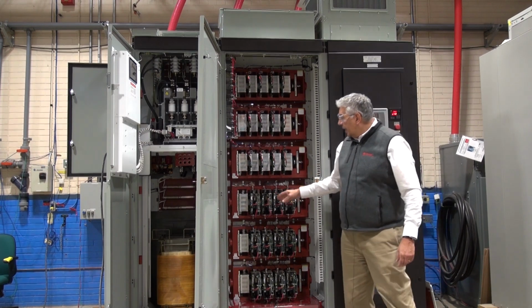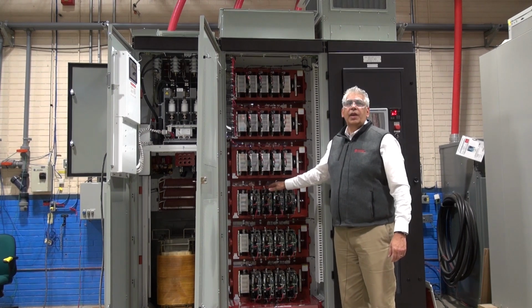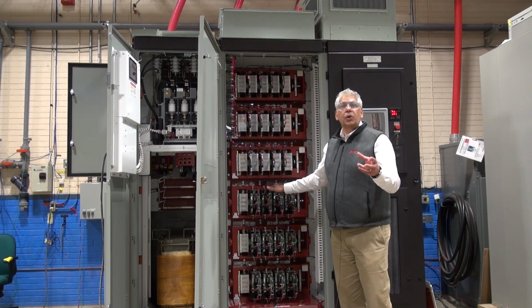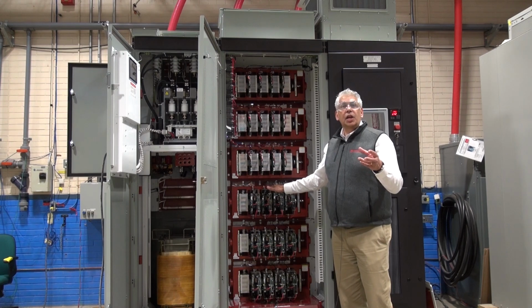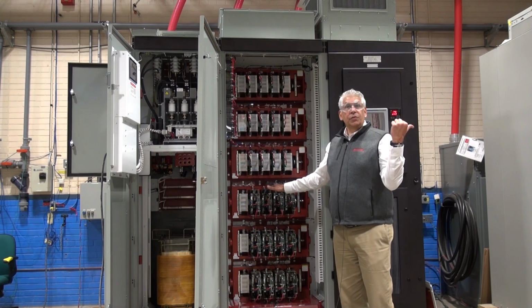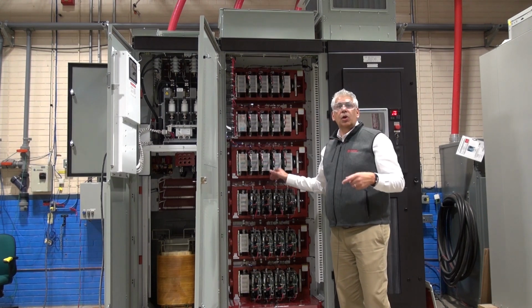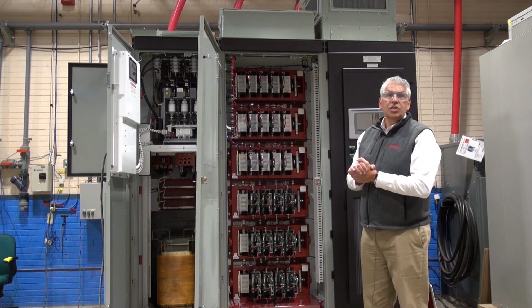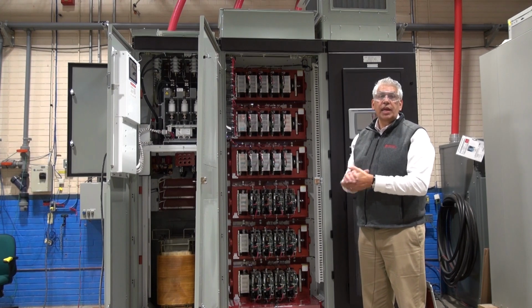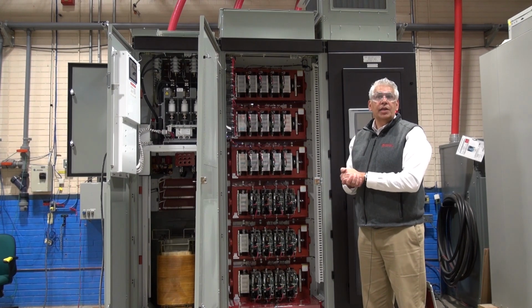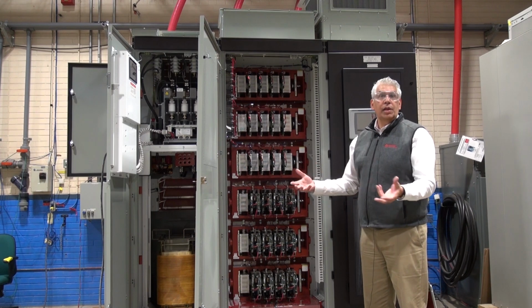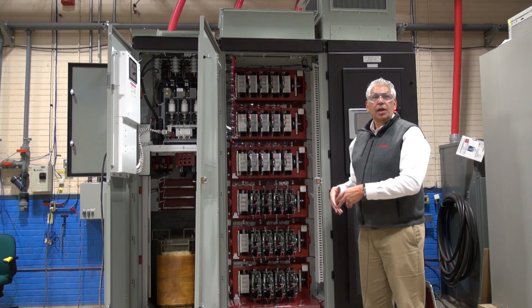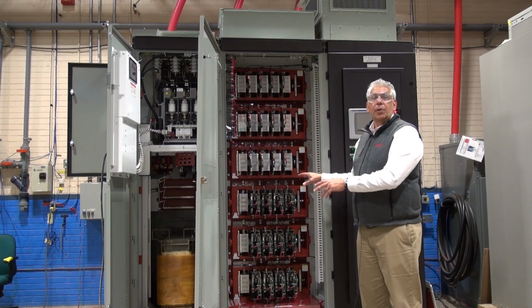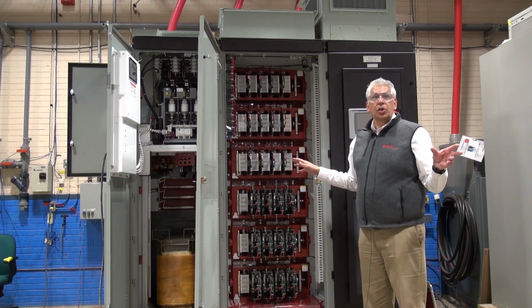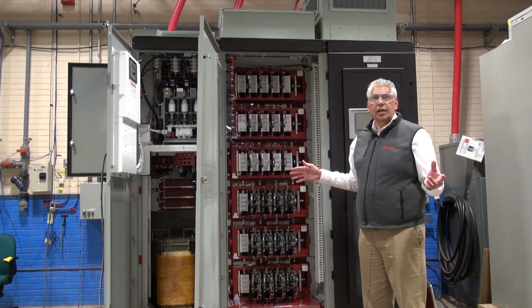When you look at the SGCTs, there are a couple of real advantages. It's symmetrical. That means it can conduct power to the motor from the utility grid and from the motor back to the utility grid. So if you require applications that need regen braking, it's built in. If you've got applications such as downhill conveyors that are operating in a regen mode all the time, this provides that 4-quadrant operation without any additional hardware, without any additional cost.